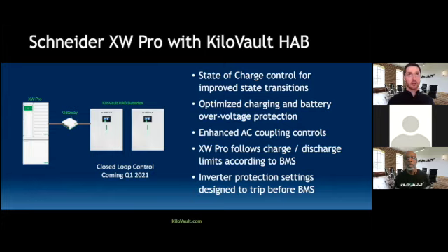And you'll see in the market today, a lot of lithium ion batteries are starting to develop closed loop communications. What this does is it allows the batteries to digitally report their voltage, state of charge, and temperature data directly to the inverter instead of relying on the inverter's voltage sense at its terminals, which is really beneficial because then you don't need to be worried about voltage drop over your home run cables.